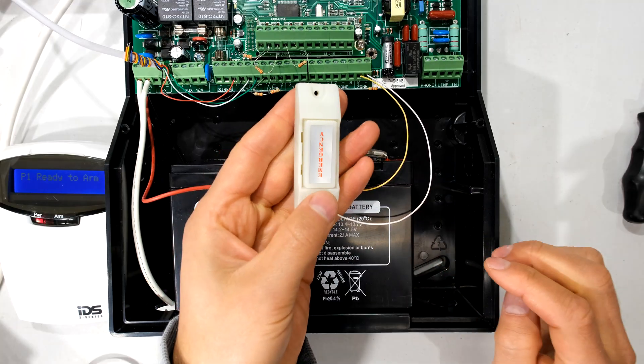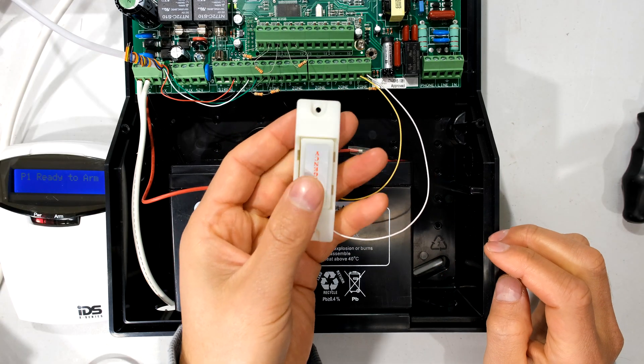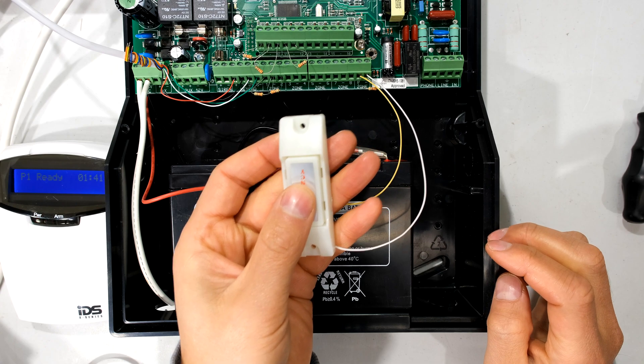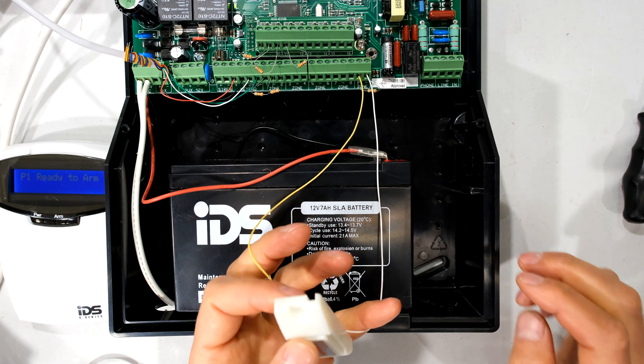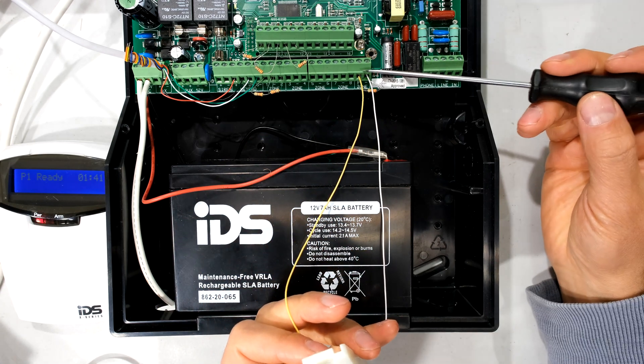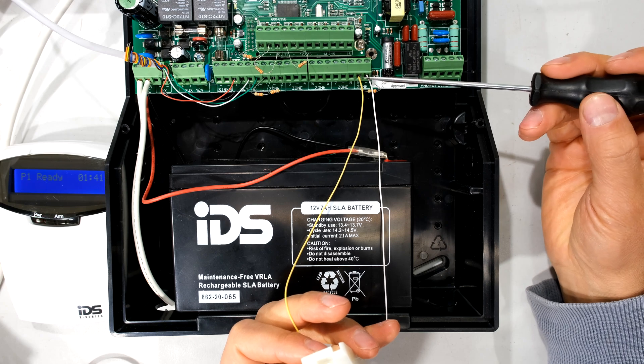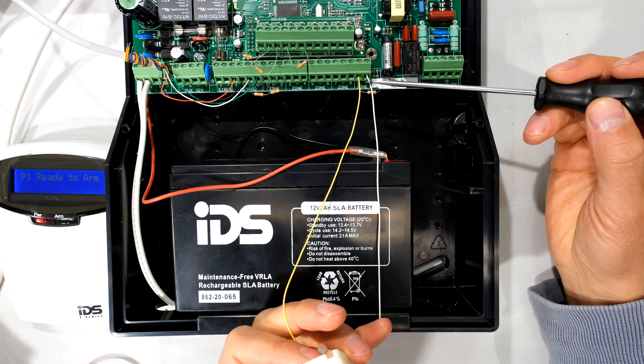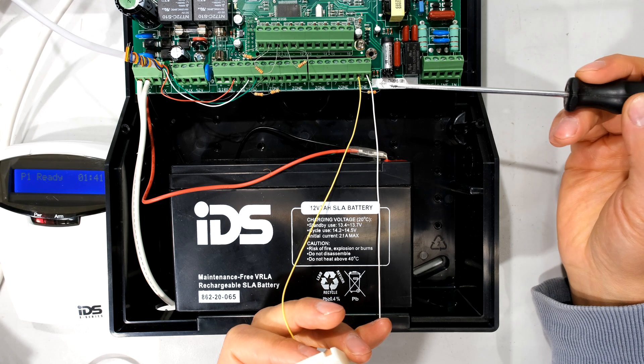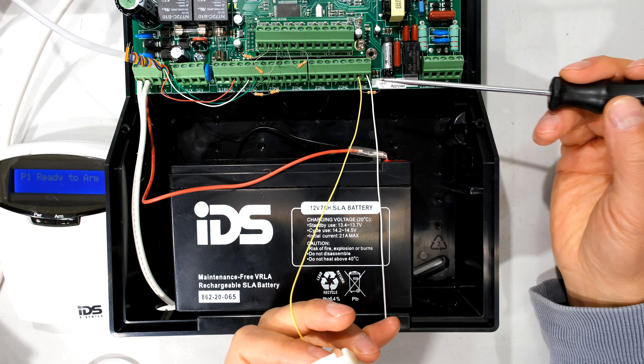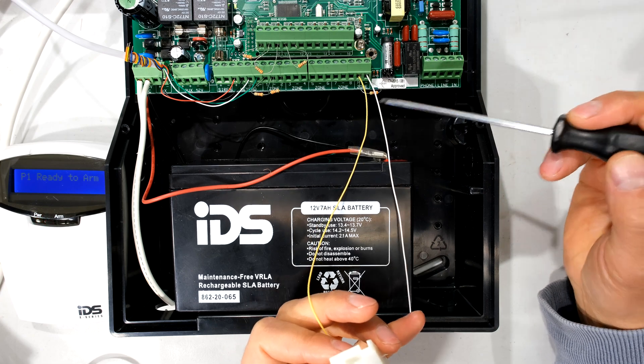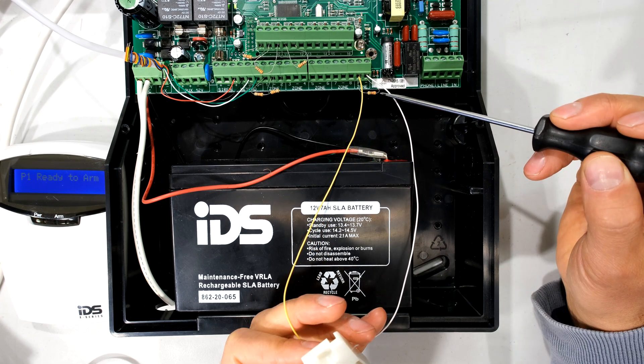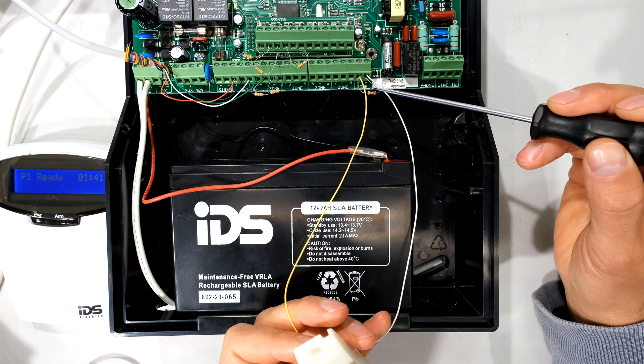Now there's the panic button and when I depress it what it does is it is shorting out the terminal there. So what that means is that under normal circumstances the terminals there should be seeing a resistor of 3.3 kilo ohms.